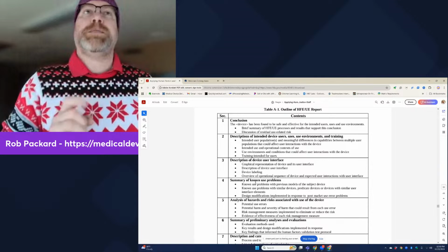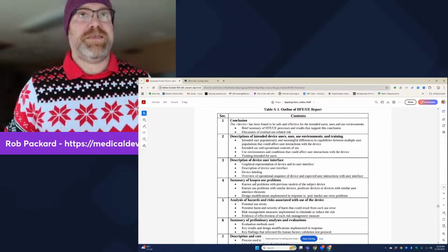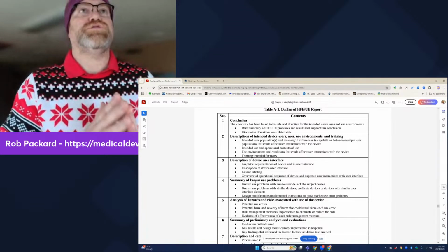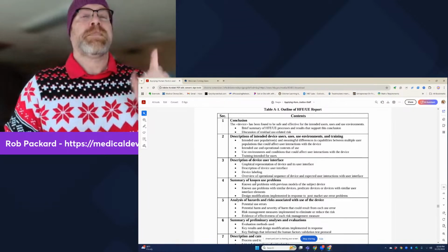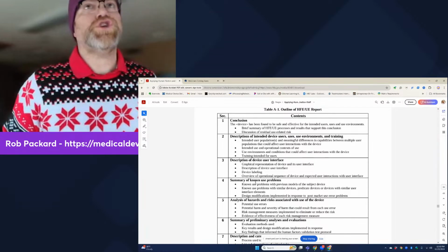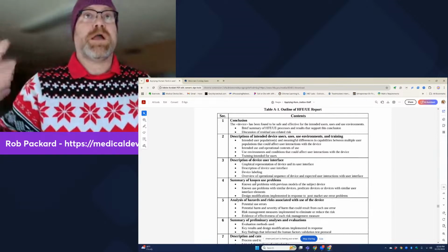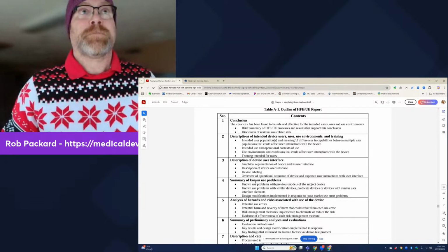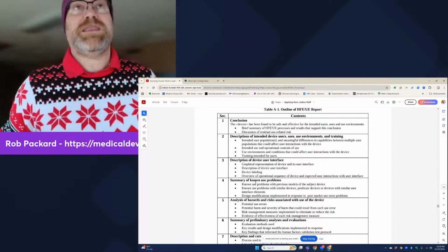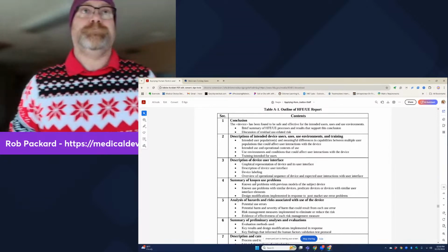Do not recruit the minimum. So FDA says minimum of 15. Some other countries, minimum of 10, but the FDA says 15 users in each user group. Do not recruit just 15 because somebody won't show up. Trust me, you're asking a bunch of people to come and take a test, but they don't need it. You need it. So if I don't need it, why would I show up? Your gift card is not enough to make me show up.